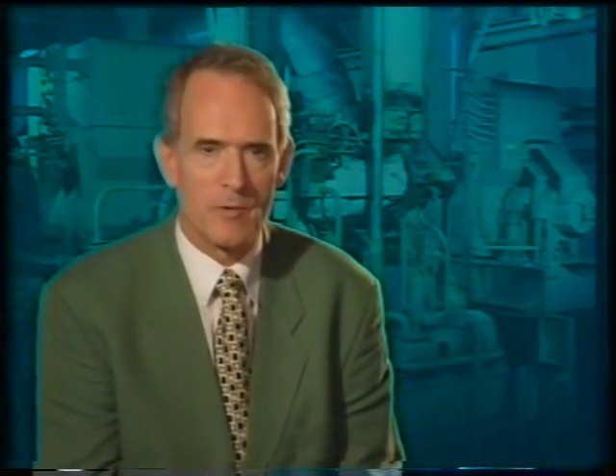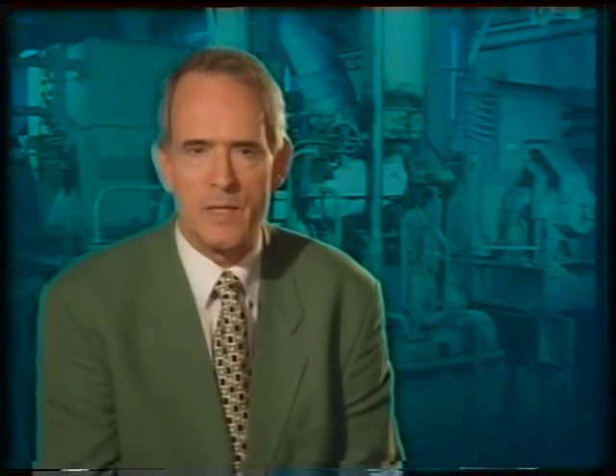This is Programme 3 of VideoTel's series on practical marine electrical knowledge. The series is made up of 8 programmes. Programme 3 deals with the main power sources and their circuit breakers, including synchronising, load sharing, fault-finding techniques and remedies. Also, test procedures on a circuit breaker if it fails to close normally.